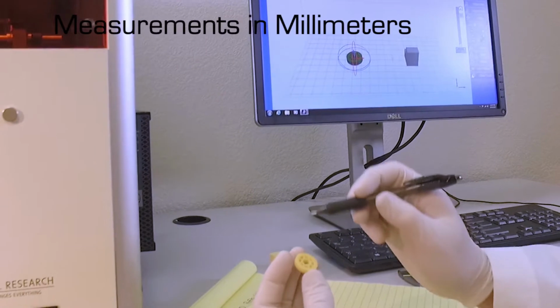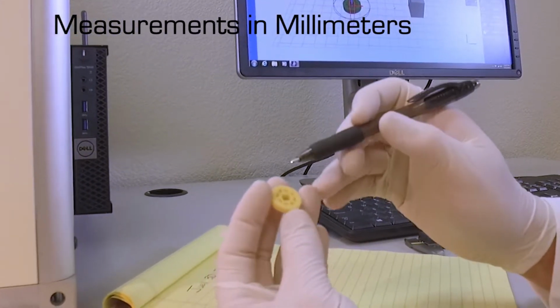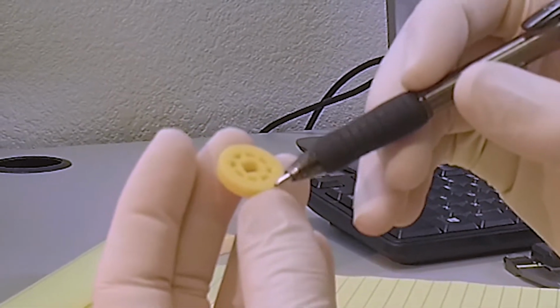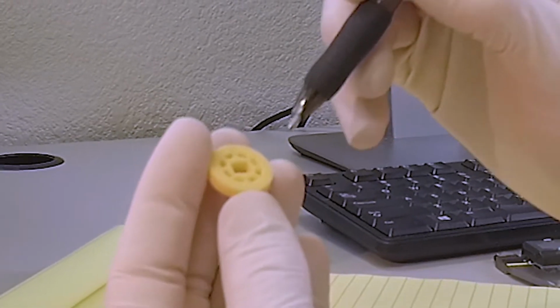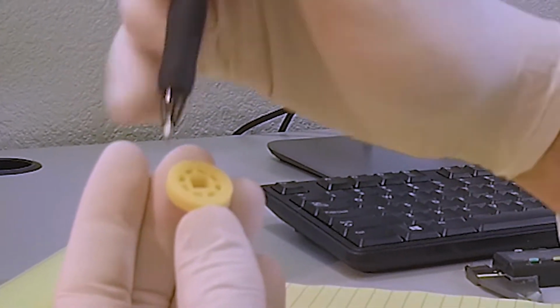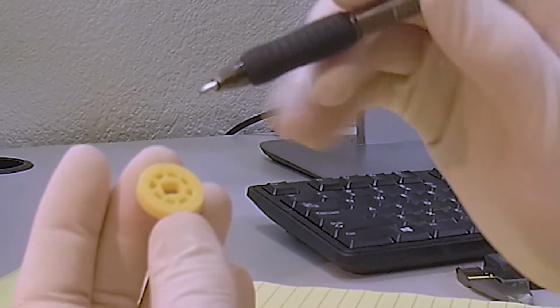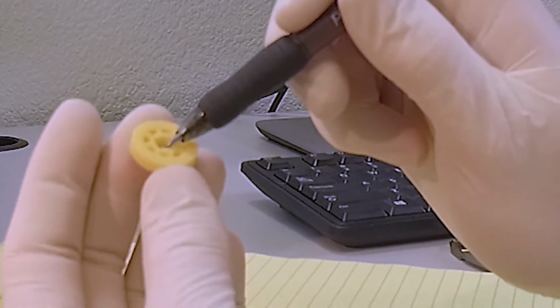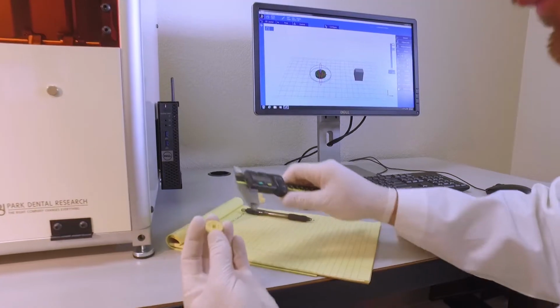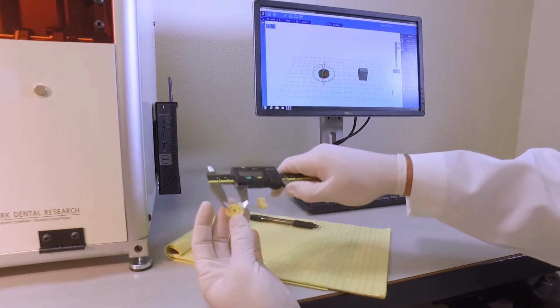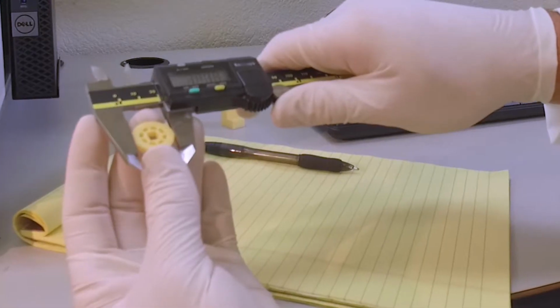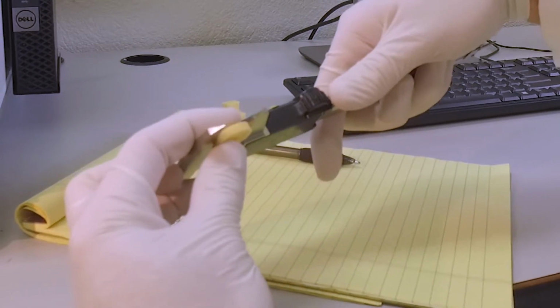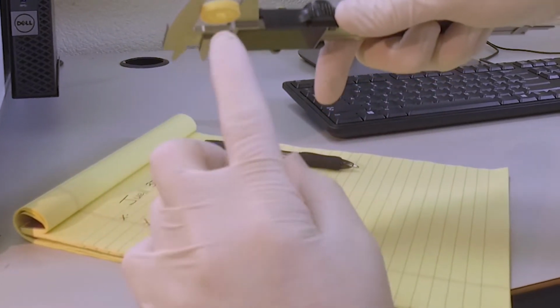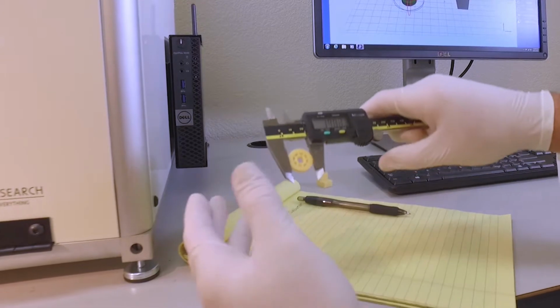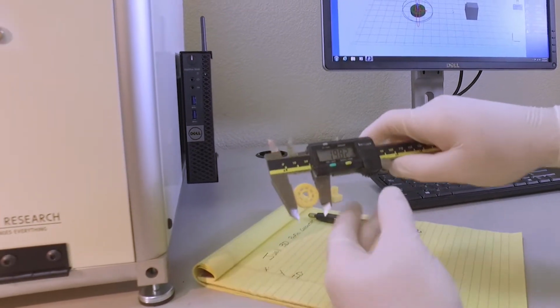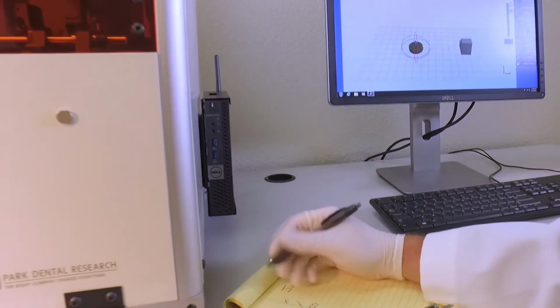We're going to measure this calibration part in 3 different directions. We're going to measure the X for the outer from there to there, and the Y on the outer from here to here. We're going to measure the X of the inner dimension from here to here. We'll measure the OD on the X first, and we want to make sure we only measure the top half of this part. This particular direction is 19.82, so I'll write that down here.